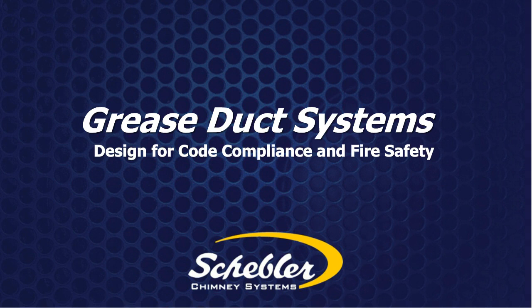Can you vent multiple hoods in one duct? Yes, I should be careful how I want to phrase that. Nowadays we see a lot of hoods with multiple connections, and we can combine those. I think it becomes a lot of questions on grabbing multiple hoods and running them in there because you can't run any kind of fire damper in there. So I'm going to say in most cases no, but I can have a hood with multiple pickup locations and run those in one duct.